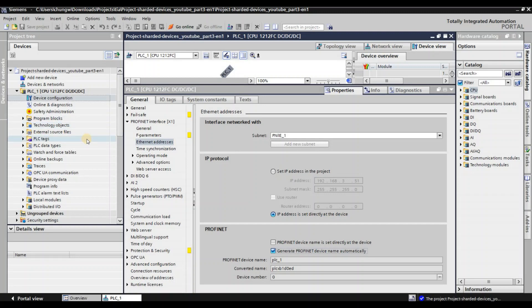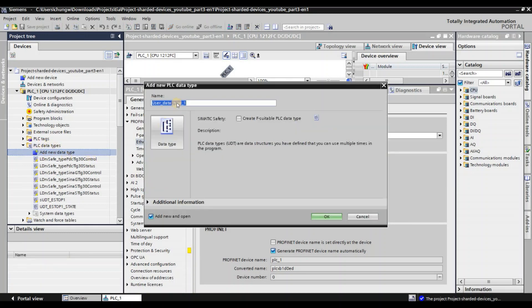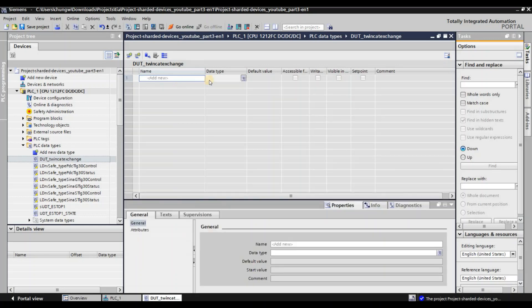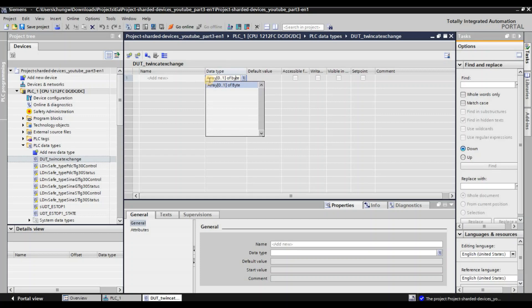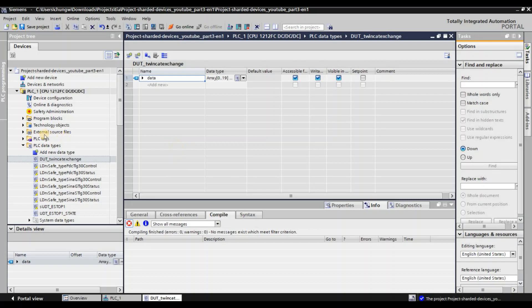Next, we need to define the tags to exchange data between TwinCAT and our Siemens CPU. But before that, I would like to define a data type first. Go to PLC Data Types, add a new data type, and enter your data type name — for example, 'TwinCAT Exchange.' Remember we defined 20 bytes, so go to array, define an array, choose Byte, and set it to index 19. Now we have 20 bytes. Change the name to 'data' and compile it. No error.